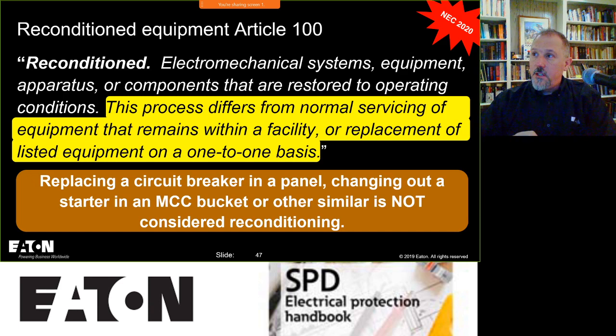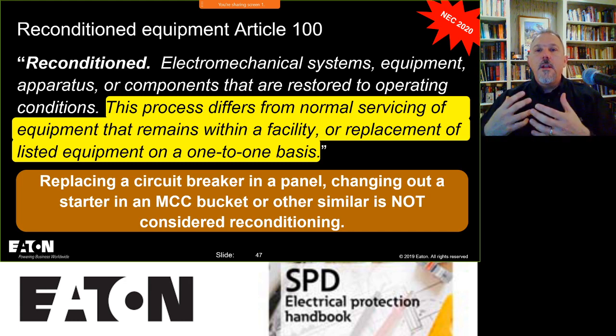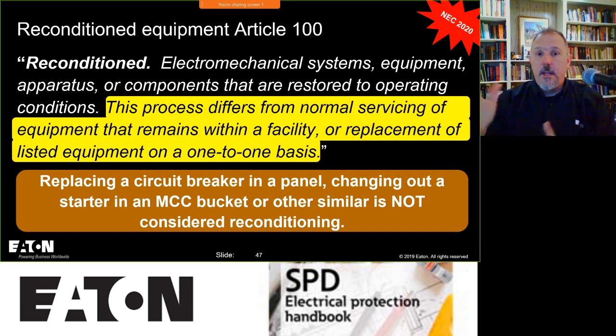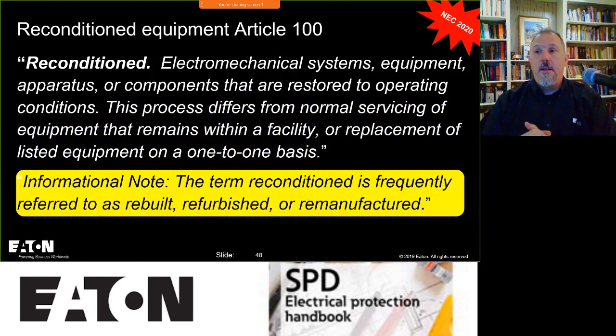You've got to look at this definition. Even if you want to call what you're doing to your equipment reconditioned, if it doesn't meet this definition, the National Electrical Code is not going to consider it as being reconditioned. Now, that doesn't mean you still can't do some of the things the NEC is telling you to do, because it's good for safety, but it just means an authority having jurisdiction or electrical inspector would not be able to cite the NEC as a violation of what you're doing, because you haven't met this definition. Hopefully that makes sense. And like I say, everybody has an opinion on that one.